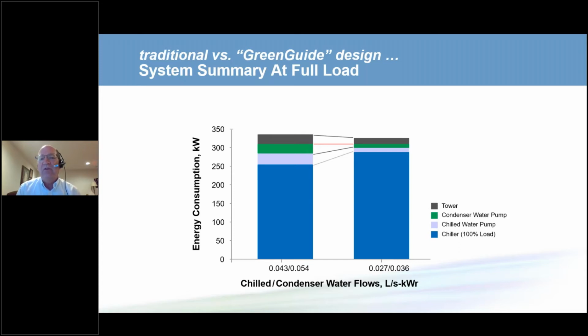What happens to the power? On the right is the ASHRAE GreenGuide flow rates. And the first thing most people notice about that graphic is the chiller power went up. And I always like to ask the question when we're face-to-face and in person, is that good or is that bad? And the answer is it doesn't matter. The reason it doesn't matter is because the building owner pays not for the chiller, he or she pays for the entire system for the entire building. Therefore, as long as the total comes down, it's beneficial to the building owner and it's beneficial for our environment.